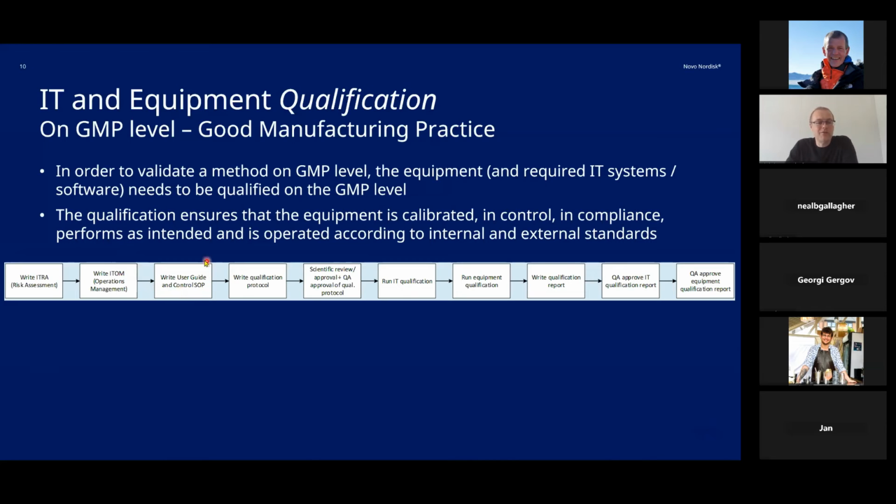Based on that, we should write user guides and control standard operating procedures on how to take measurements on the instrument. And bring that about, and then you write a qualification protocol, which again gets reviewed, and then QA will review this.